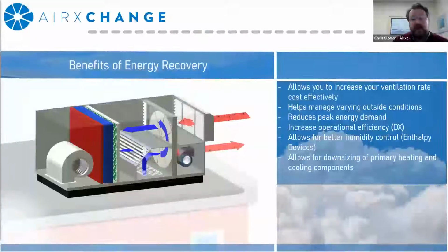So just quickly to summarize, an energy recovery device allows you to either maintain the minimum rates or increase your ventilation rate cost effectively. And in the pandemic environment, that's a very useful tool to have. We're all looking for ways to maximize ventilation. It helps you buffer the outside air conditions. So as it starts to get very hot or very cold or very humid, it helps buffer those to a more manageable point.